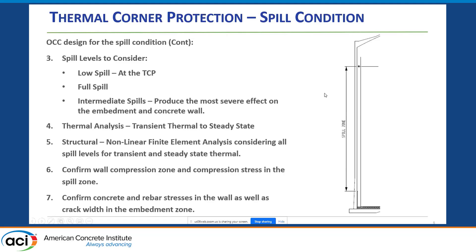We need to maintain an average compression stress of 145 pounds per square inch. Based on that, the tank will remain liquid tight and substantially gas tight during the spill event. In the spill analysis, we need to consider a multiple range of spills, including a low spill at the TCP embed location, a full spill when the inner tank empties completely into the annular space, and intermediate spills that produce the most severe effect on the embedment in the concrete wall. The spill analysis needs to consider the thermal effect of the transient thermal that occurs during the spill and through the steady state, requiring a structural nonlinear finite element analysis.